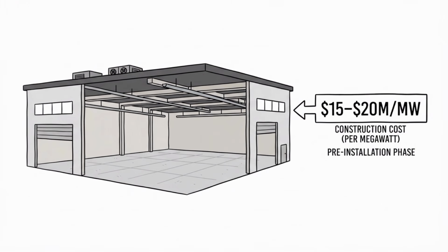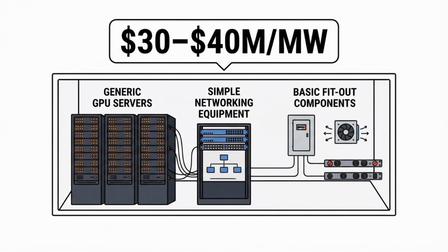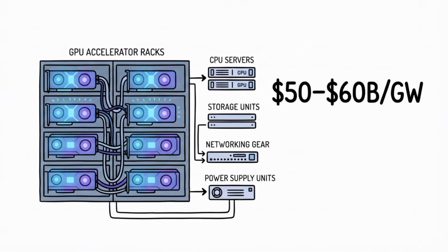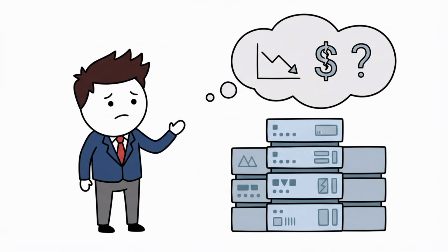Added up, shell and core construction for an AI-optimized facility runs $15 to $20 million per megawatt in 2026, before a single chip is installed. Layer in the GPUs, the networking, and the fit-out, and the fully built cost climbs to $30 to $40 million per megawatt. That's the full package Huang was pricing at $50 to $60 billion per gigawatt. His own hardware, he said, accounts for well over half of it.